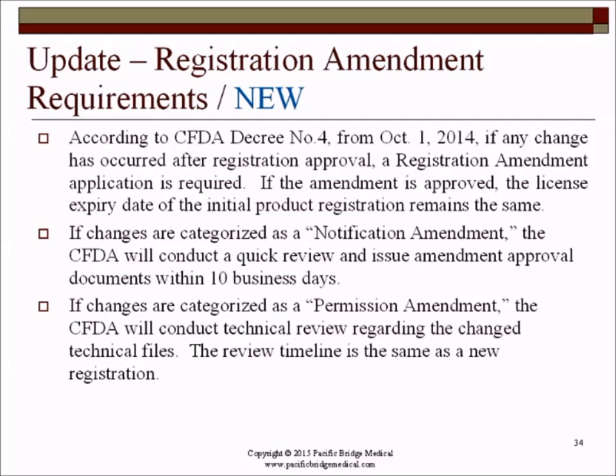And then if changes are categorized as permission amendments, the CFDA will conduct a technical review regarding the changed technical files. So this is going to happen if there's a change of product model, composition of the product, or the product structure, let's say, if there's a change in the product technical specifications, or a change of the manufacturing site location, or there's some change in the product for its intended use, then you're going to look at the situation of the permission amendments.